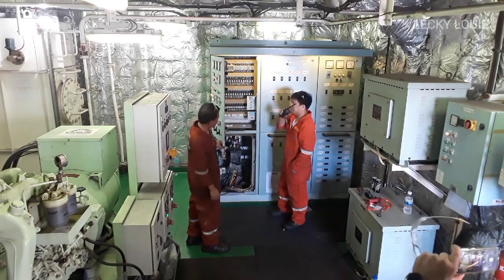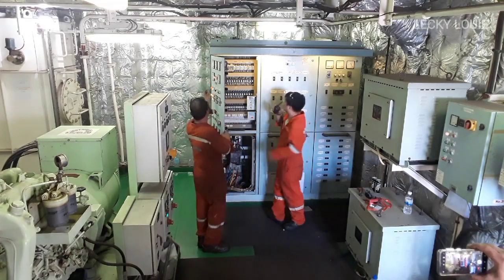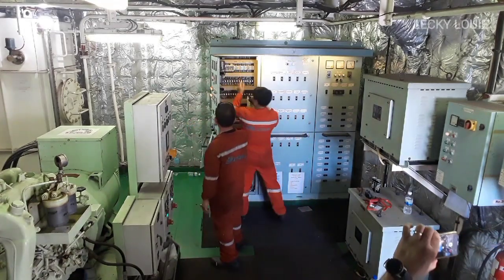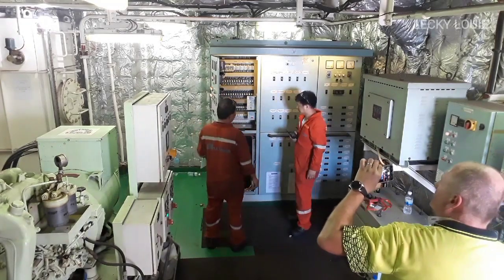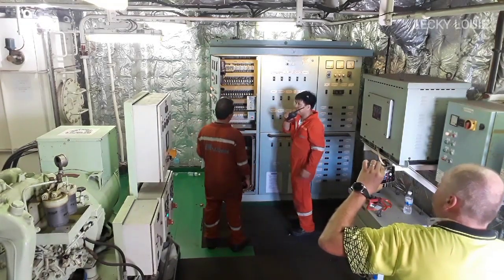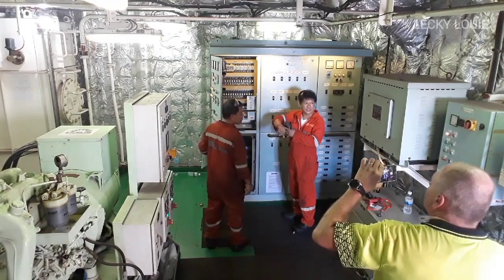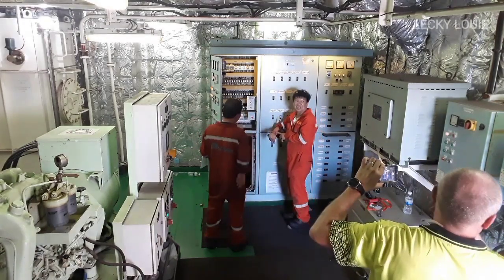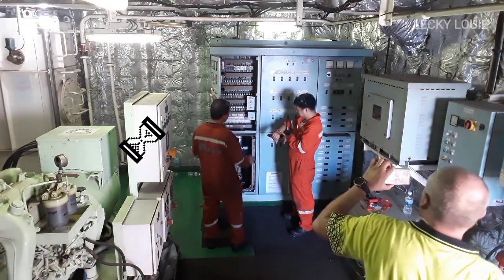For our last test, we will measure the time it takes to connect to the bus bar, because as per SOLAS regulation, it should be less than 45 seconds after the blackout, for your backup supply to automatically connect. So now we will test how long it takes to connect to the bus bar.